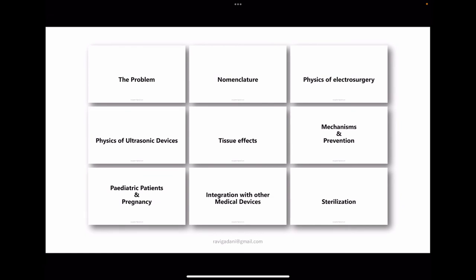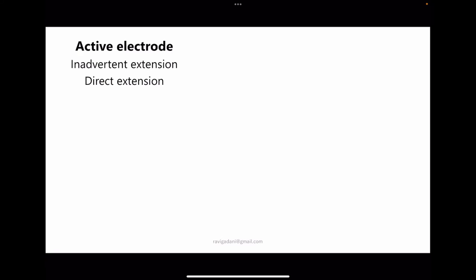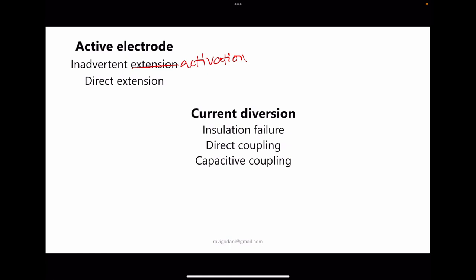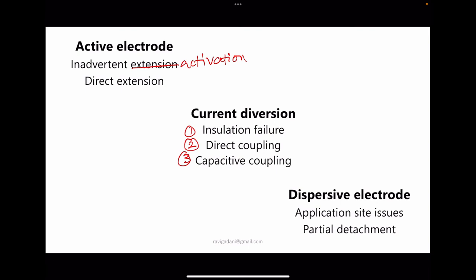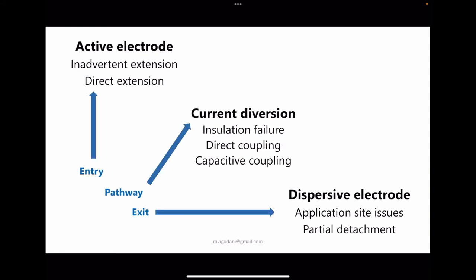Surgical energy can cause injury through several mechanisms. At the active electrode level: inadvertent activation and direct extension. Through current diversion: insulation failure, direct coupling, and capacitive coupling. At the dispersive electrode level: application site issues or partial detachment. These can be remembered as entry-level issues, pathway-level issues, and exit-level issues.